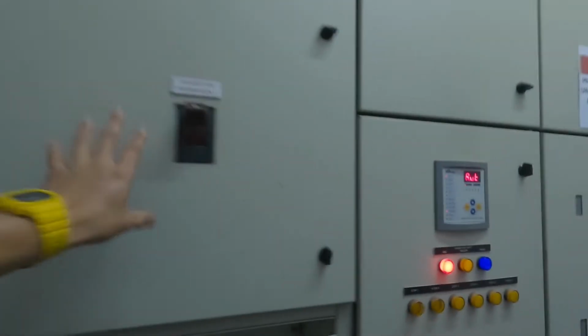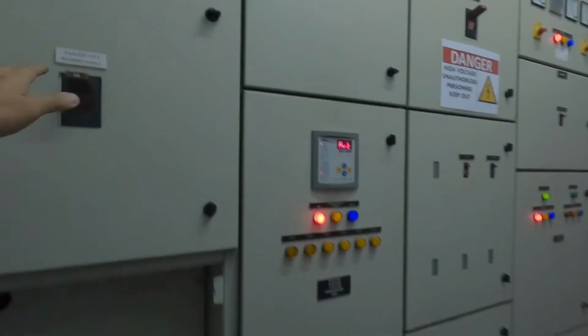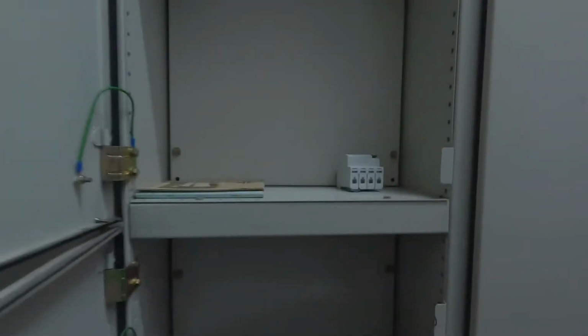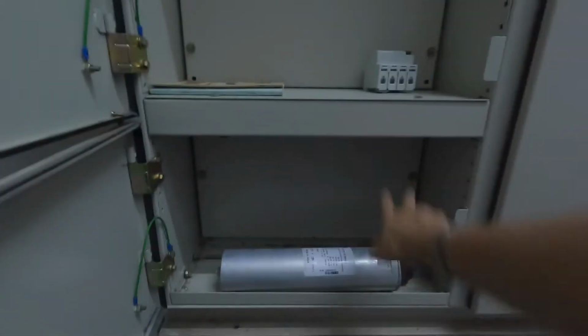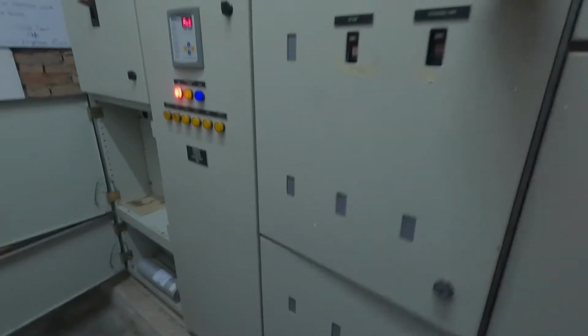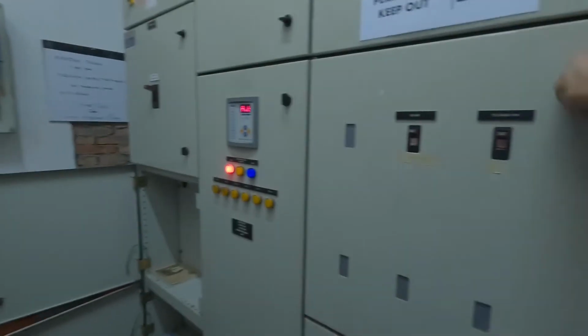Second thing, at this main electrical panel there aren't any surge protection device. Okay, like what we are seeing here, there's no surge protection device installed at the main incomer panel. And also here, there's no electrical surge protection device. Okay, it is advisable to install at the main board as it also complies to the regulations. Alright, so now after checking here, we check the ATS panel.